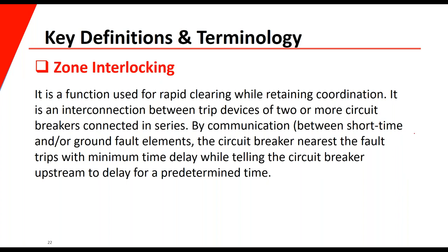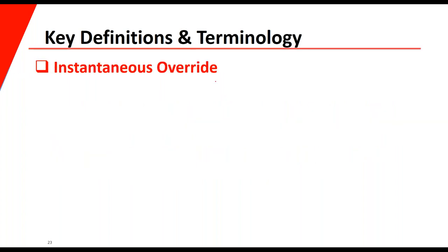Zone interlocking is a function found on some trip devices used for rapid clearing while retaining coordination. It's an interconnection between trip devices of two or more breakers connected in series. By communication between the short time or ground fault trip elements, the circuit breaker nearest the fault trips with minimum time delay while telling the upstream circuit breaker to delay for a predetermined time — basically saying, 'I'm going to trip; the fault is behind me. If I don't trip, then you go ahead and trip.' A lot of facilities don't use zone interlocking, but in some cases it may be a useful feature.